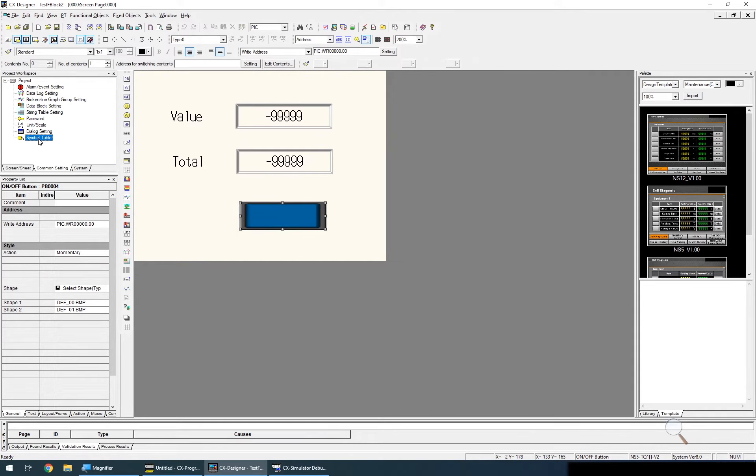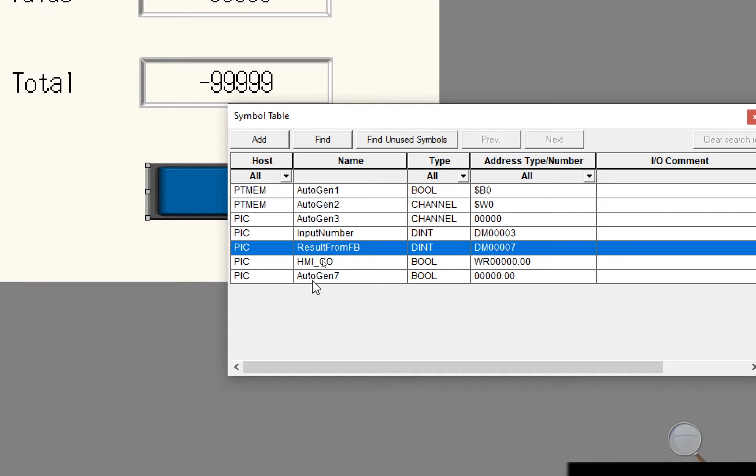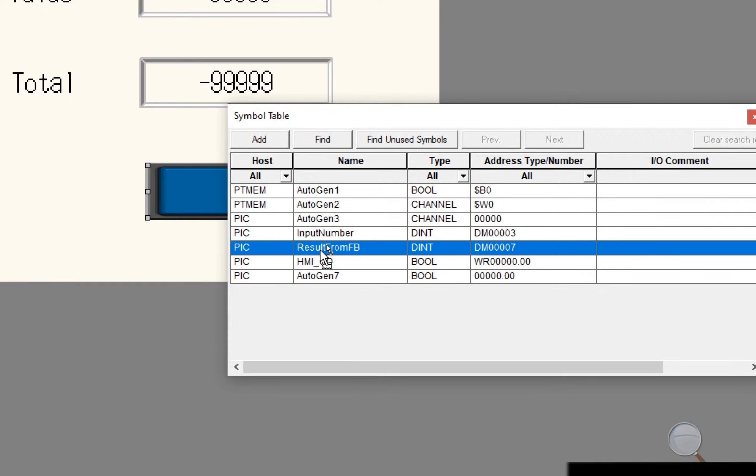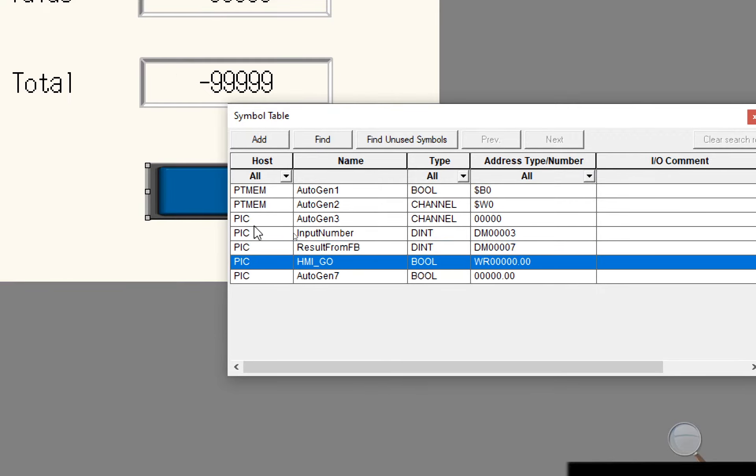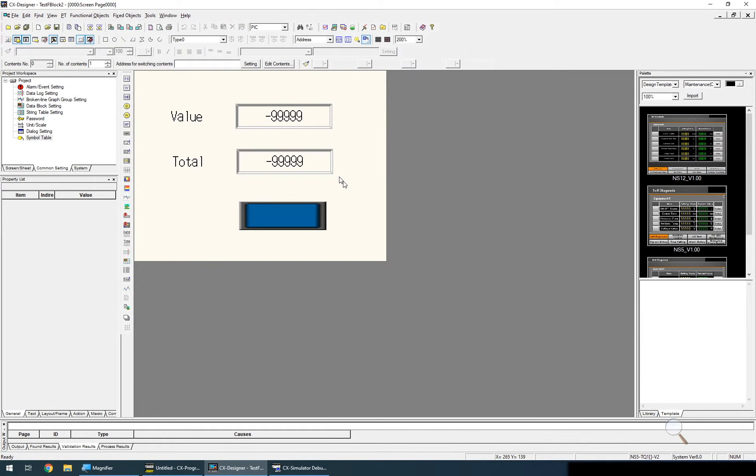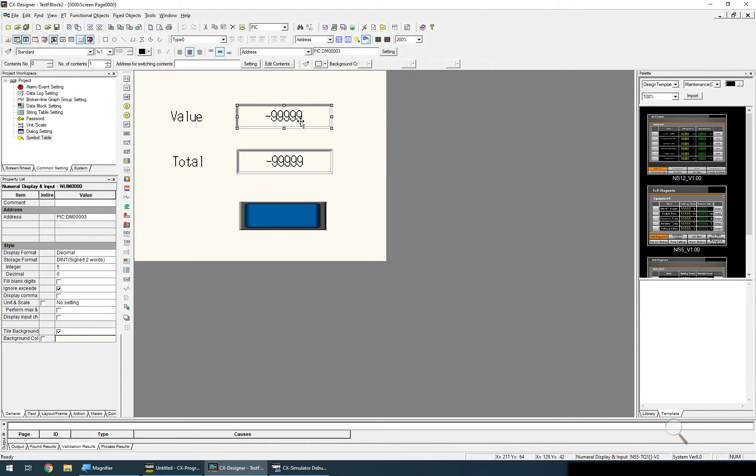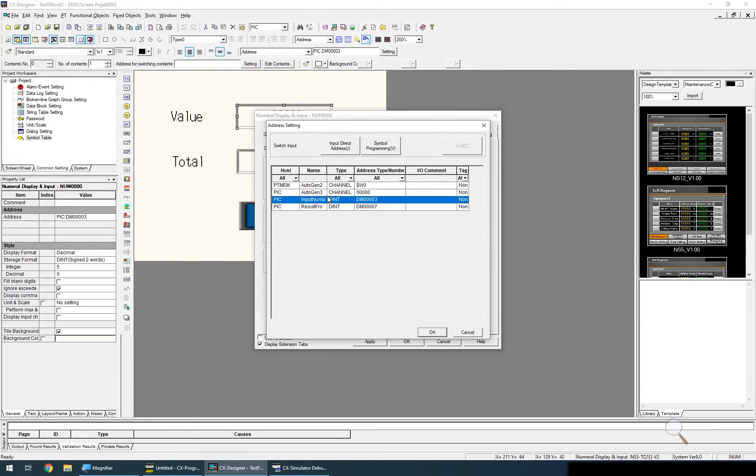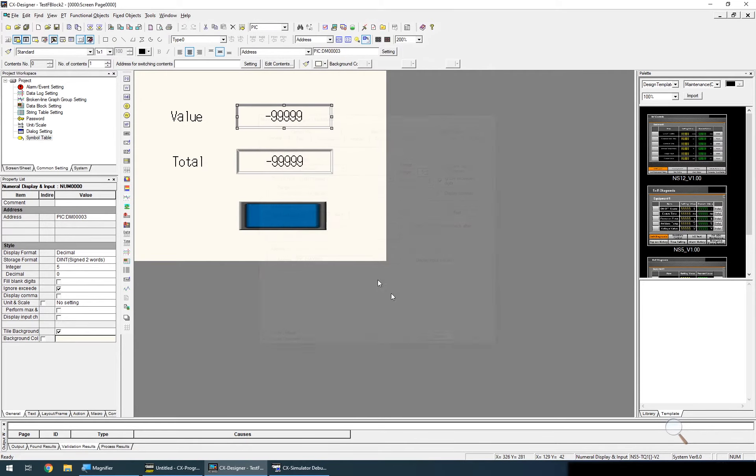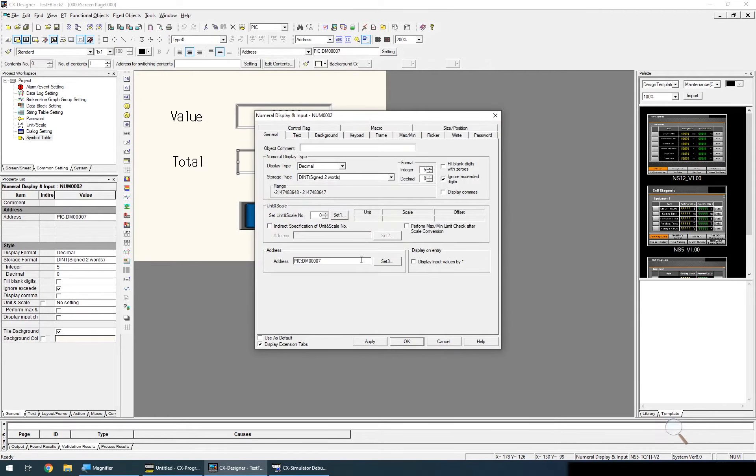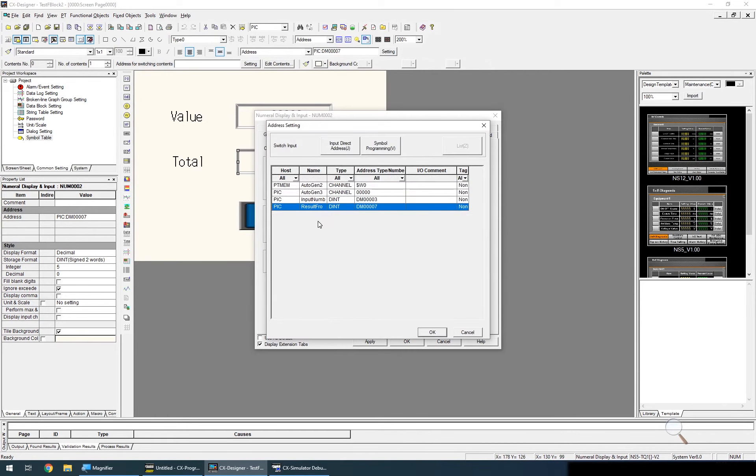I've also gone to the symbol table and I've copied in the three variables: my input number, my result from function block, and my HMI button. If I double click on the numeric input I'll just check I have it set up right and I have, it's a D int for the storage type and I've selected the correct address. And the same for this one, D int and the address I've selected is result from function block.